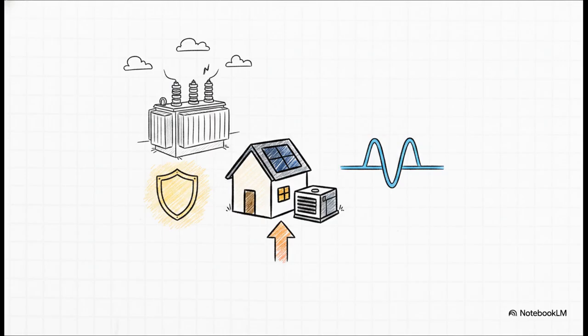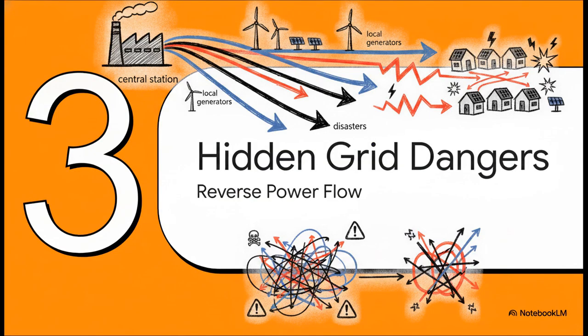By placing generation right near the load, utilities get incredible flexibility. It improves localized reliability, takes strain off existing substation transformers, and dramatically lowers transmission line losses. Because the power doesn't have to travel far, the overall voltage profile and power quality experienced by the customer are enhanced. But it's not quite that simple.